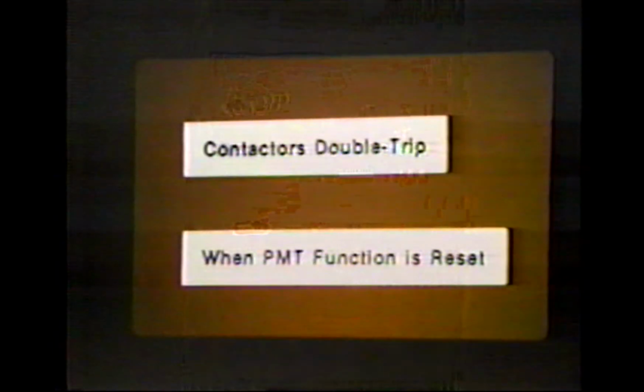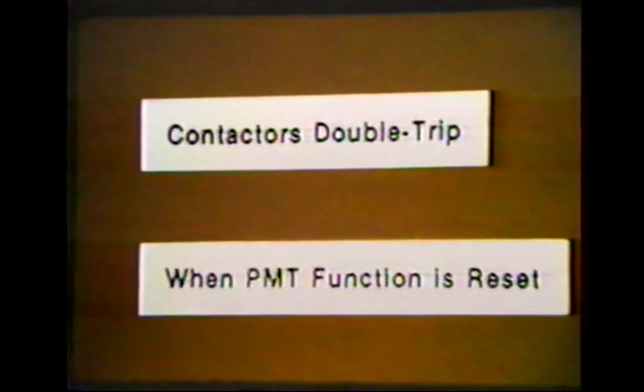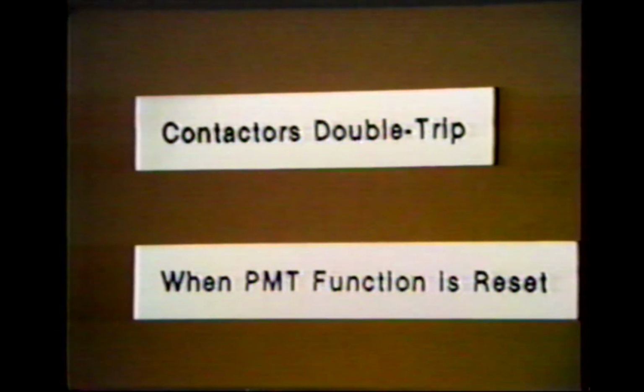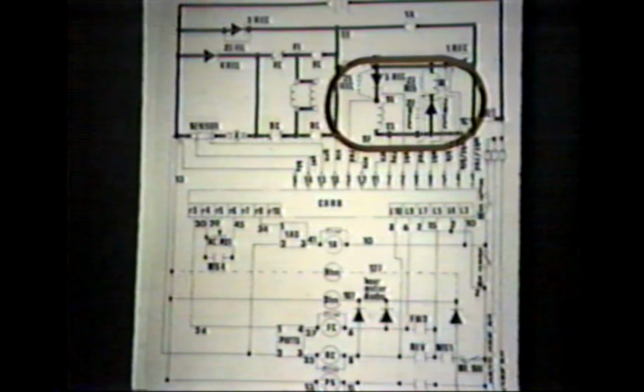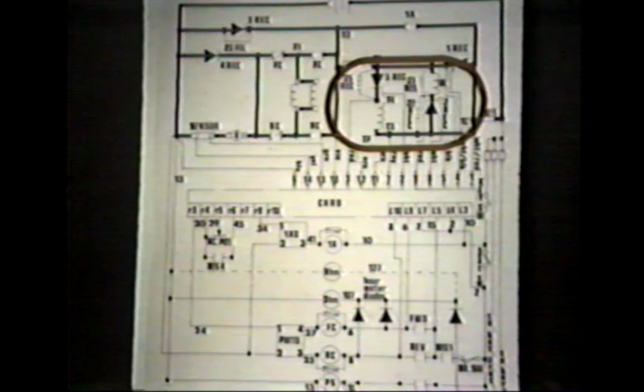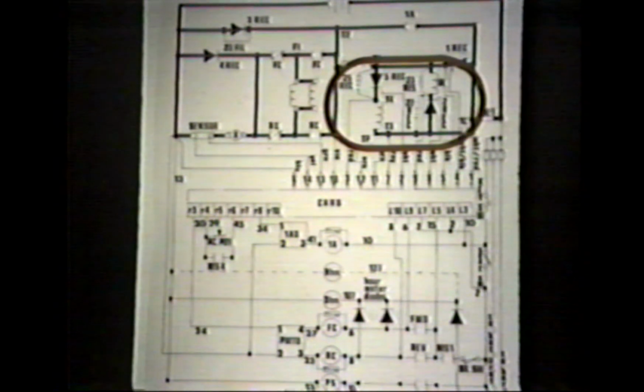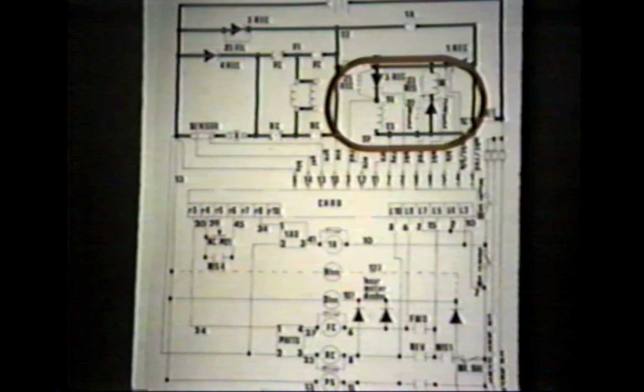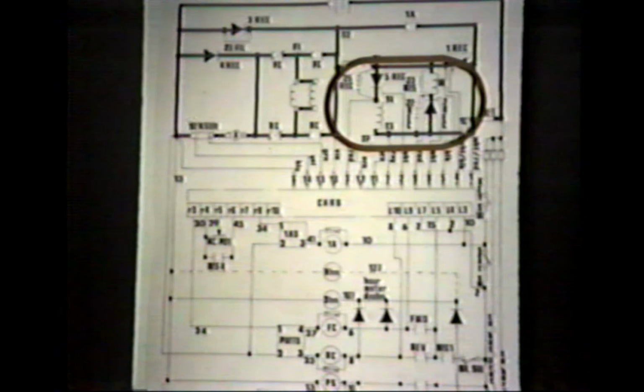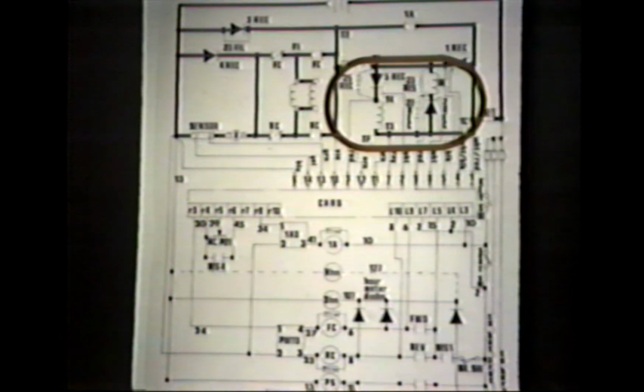Another symptom that may occur is the contactors will double or single trip every time the PMT function is reset. The problem in this case would be in the turn-off circuit, which would include the 2, 5, 22, and 25 recs, the capacitor, transformer, choke coil, and 23 resistor. The most common problems are the 22 and 25 rec snubbers. If both snubbers check good, sometimes interchanging their positions on the panel will solve the problem.